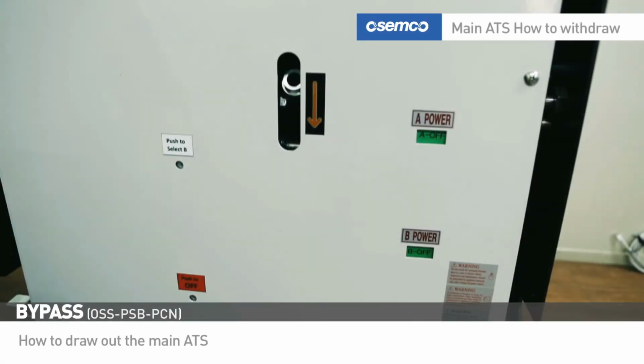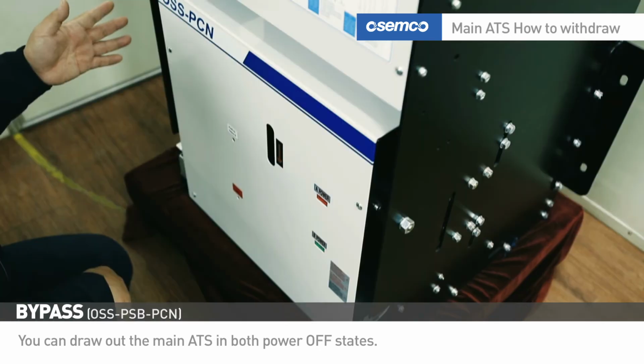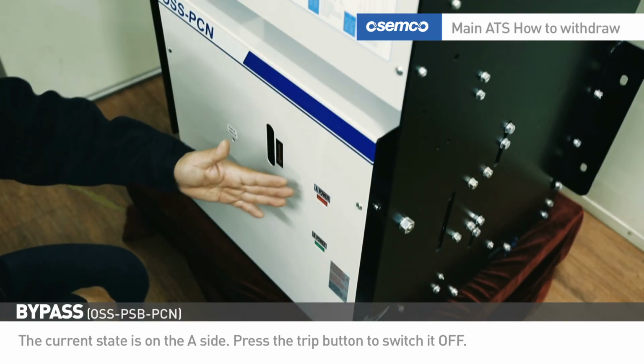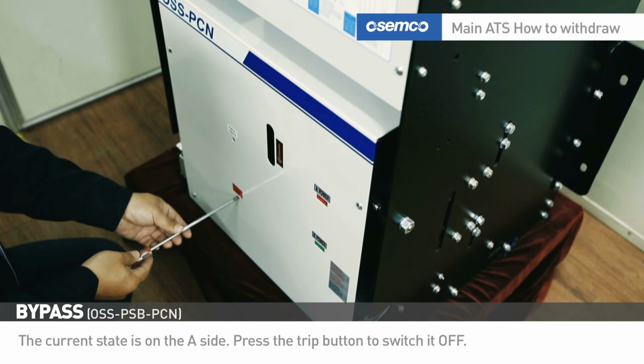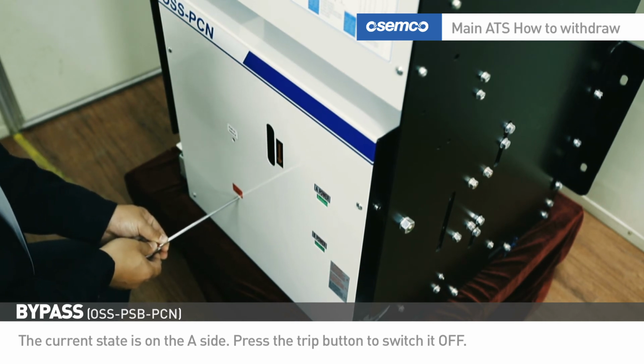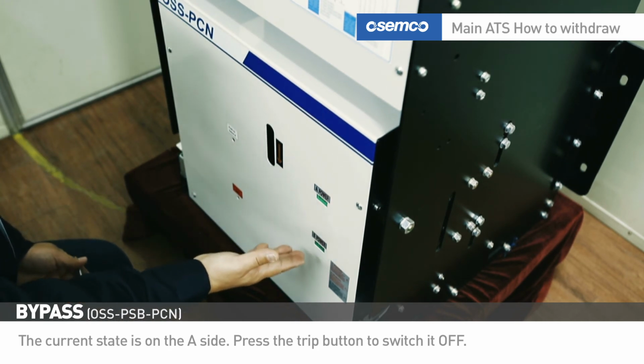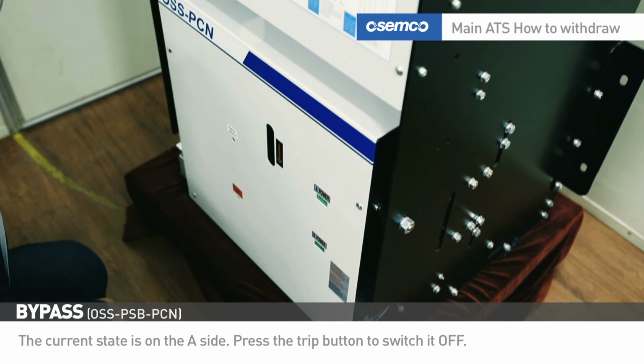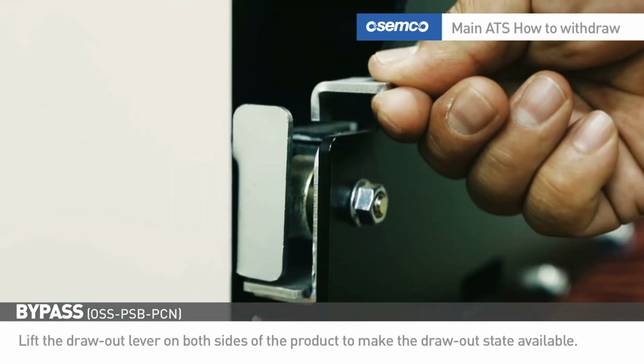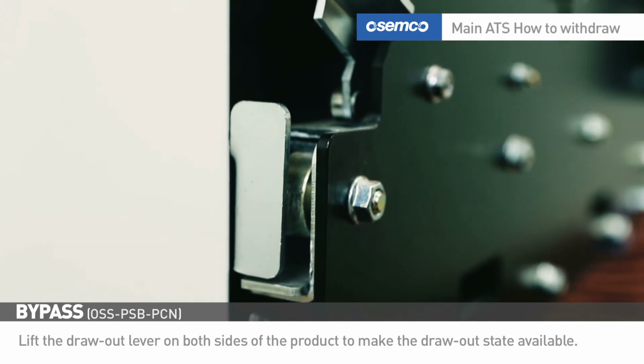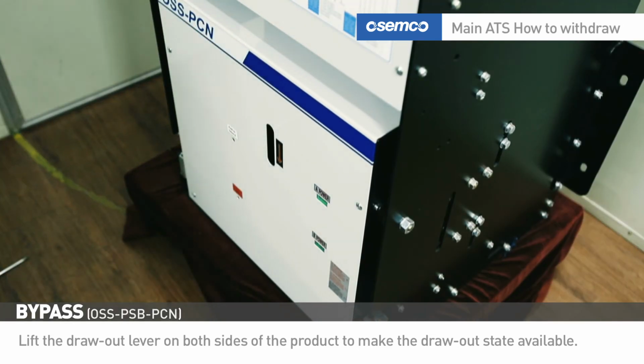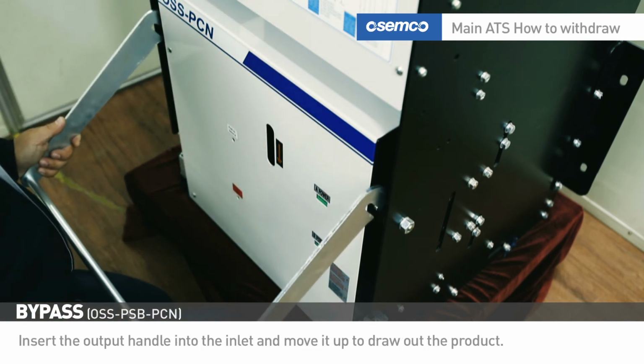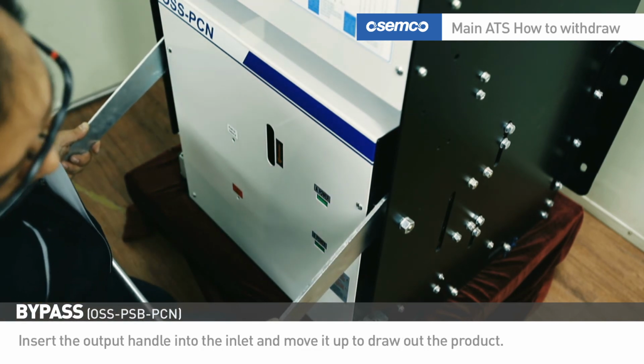How to draw out the main ATS. You can draw out the main ATS in both power-off states. The current state is on the A side. Press the trip button to switch it off. Lift the drawout lever on both sides of the product to make the drawout state available. Insert the drawout handle into the inlet and move it up to draw out the product.